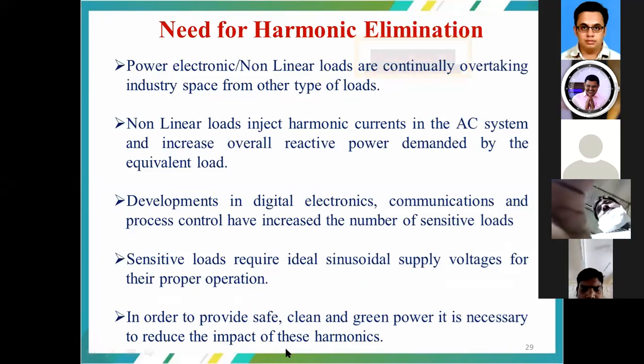So next is the need for harmonic elimination. If you are not eliminating the harmonics at the generating point itself, it is going to cause problems for the non-linear loads, and it is going to affect the systems which are all connected in parallel with the charging stations or the converter stations.